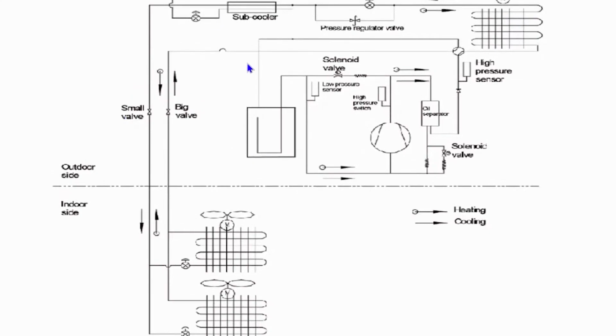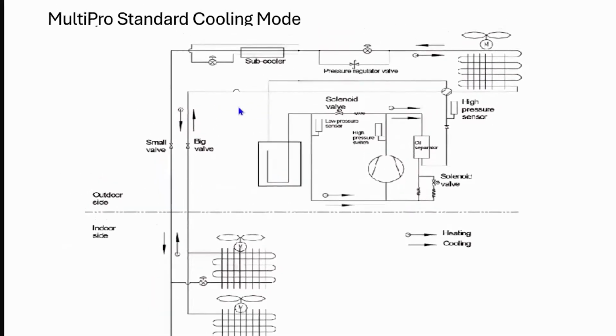When I ever get time, I would like to highlight this diagram and make it a little bit more user-friendly, easier to read. This is an example of a machine in cooling mode. And I brought this one up specifically for a reason. Because if you look out here, this is your outdoor coil. This being the outdoor coil, this unit running in cooling mode, and I actually took this call on a MultiPRO Ultra B revision. This is a standard, but the concept's the same.